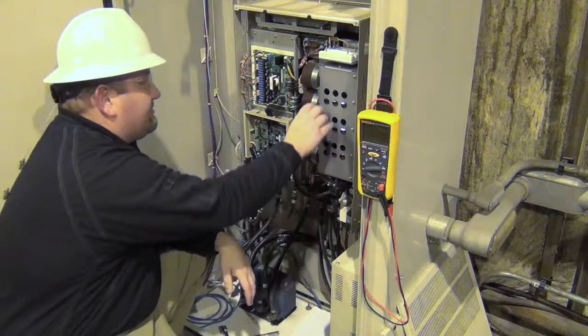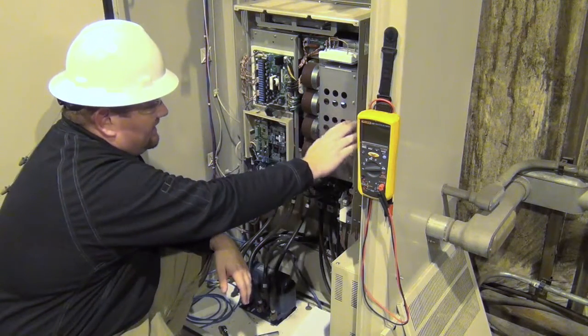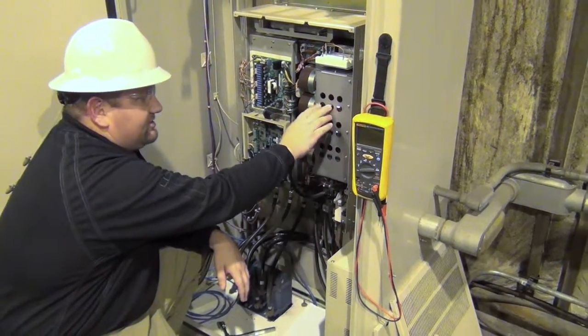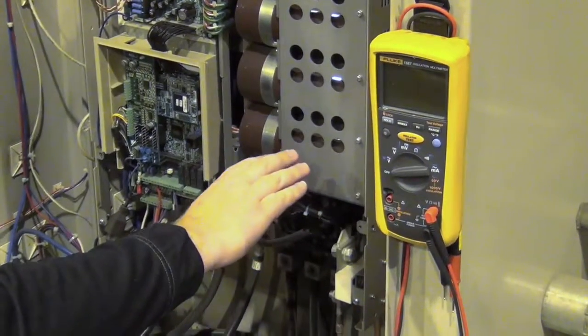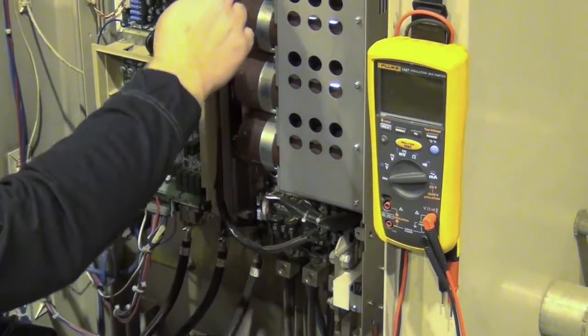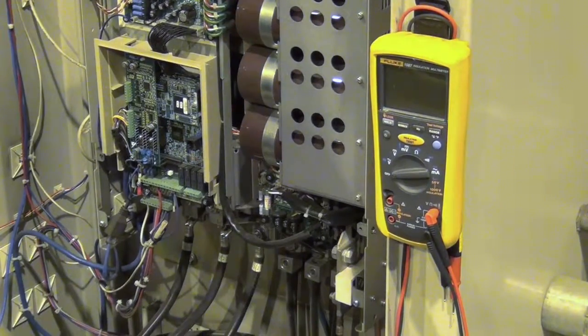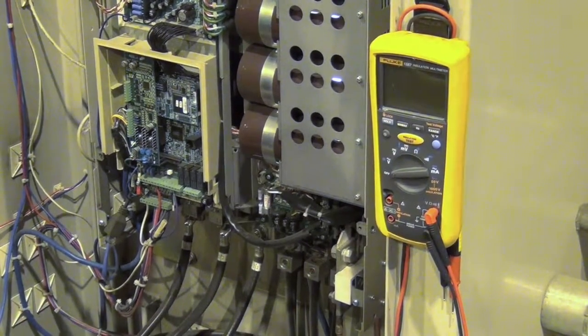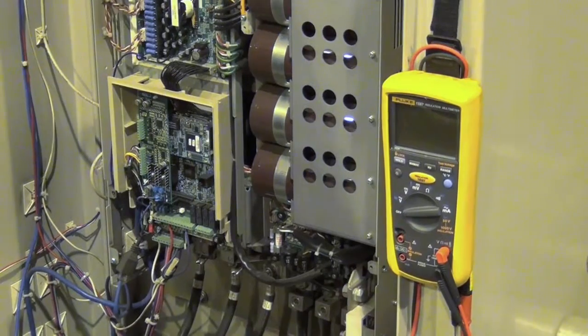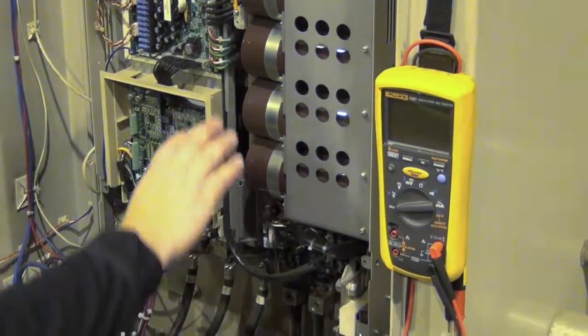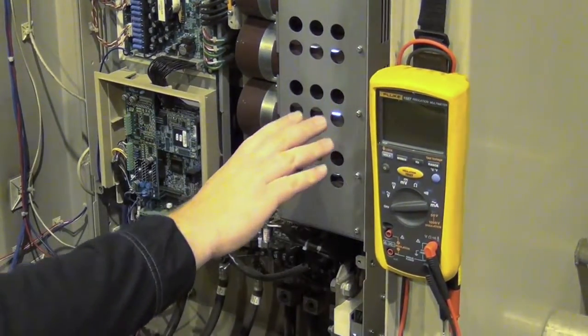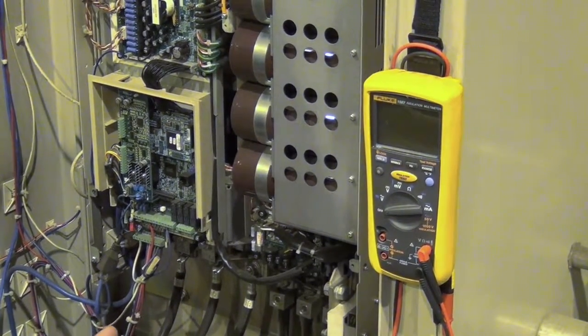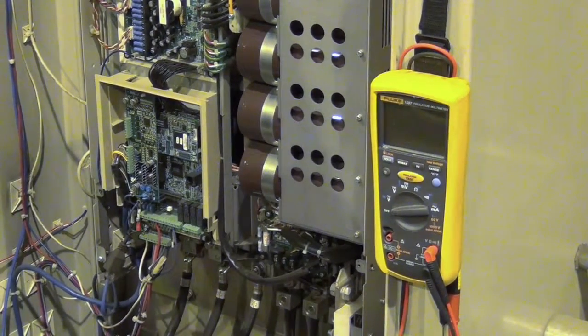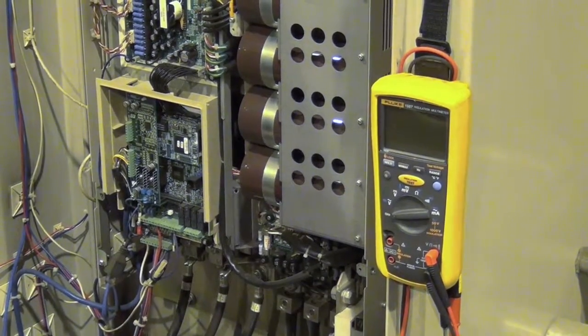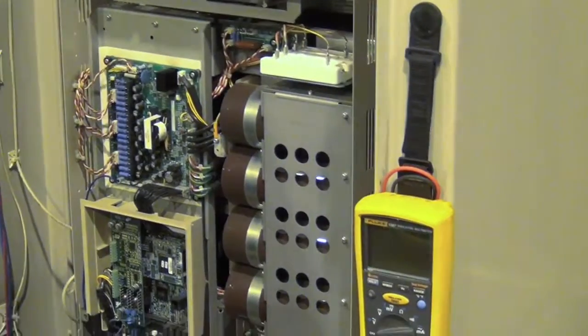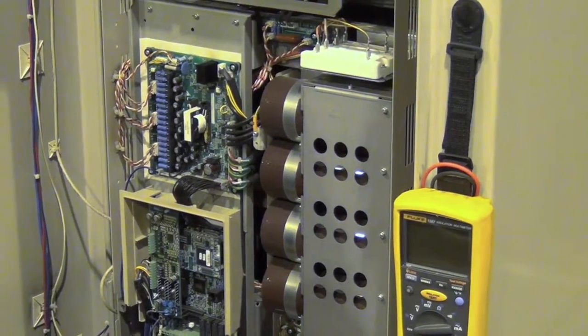But again, we're going to look at the capacitors. What we're looking for is a nice even color. It's hard to see in the video, but there's slots here that aid in being able to see the entire cap. Up at the front, there's a vent hole on each of the capacitors. None of those vents have popped out; a little tab will pop from the top. Again, we're looking for a uniform shape, uniform coloring. The older the drive, it'll likely have discolored, but you're looking for a nice uniform coloration, and any discoloration that has taken place is uniform to the entire capacitor.